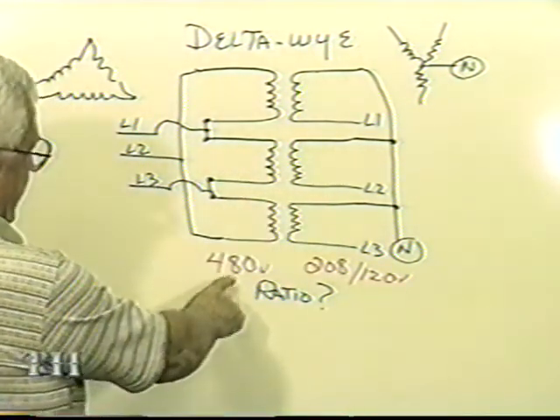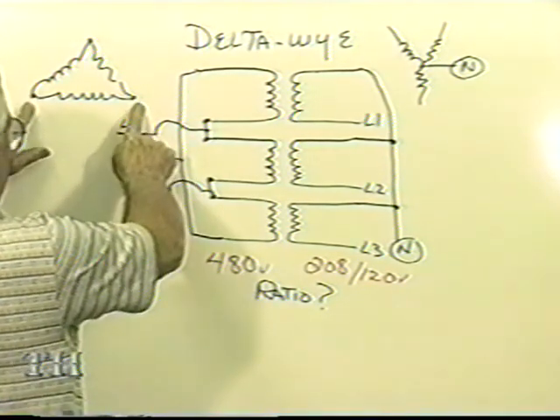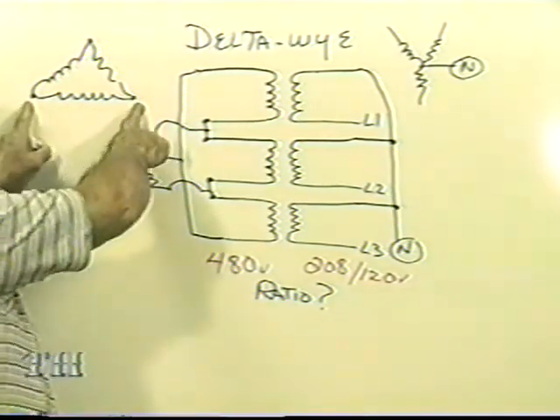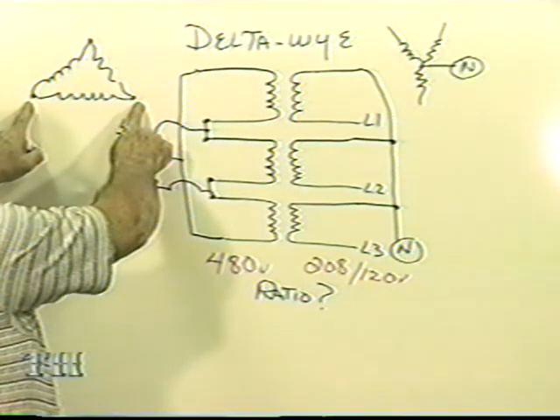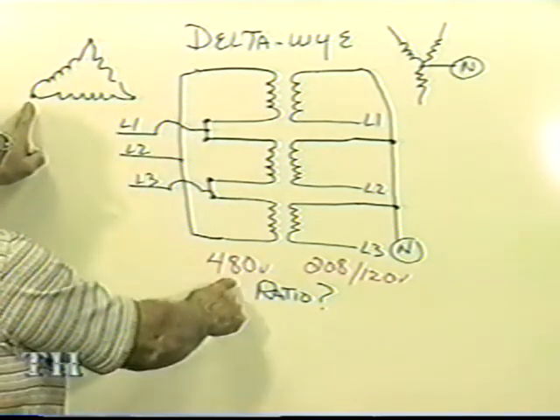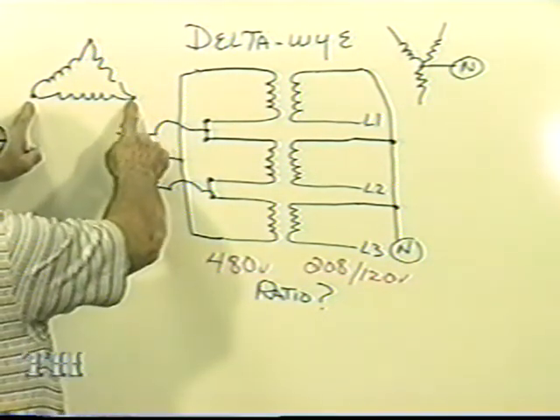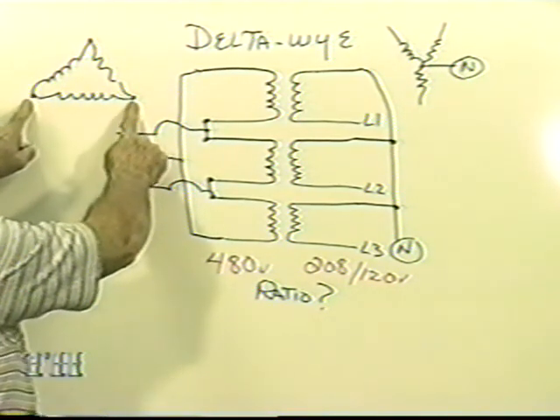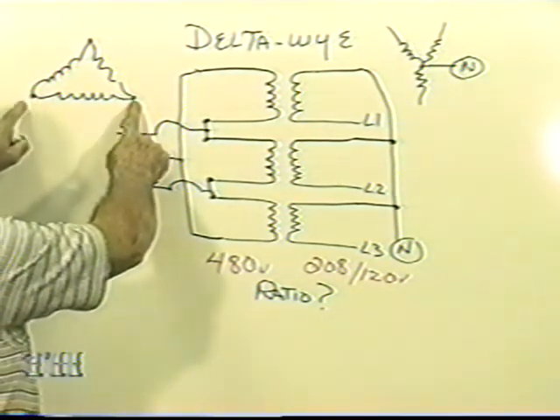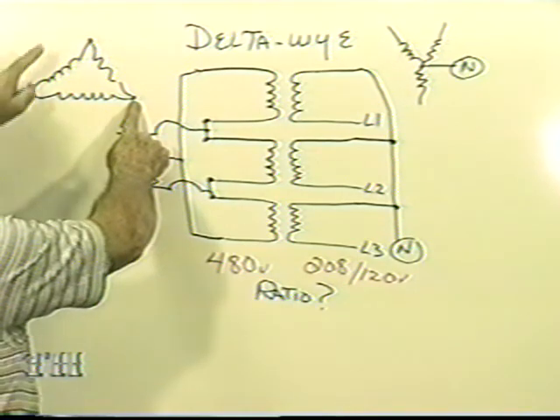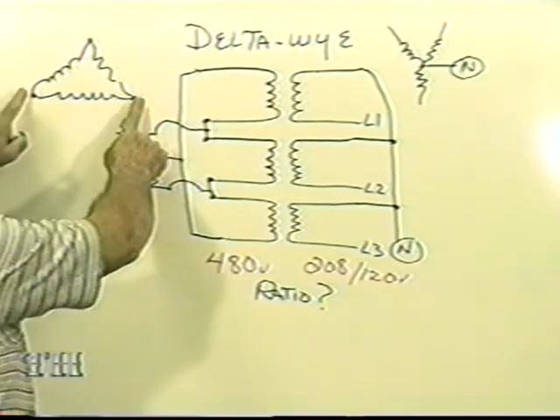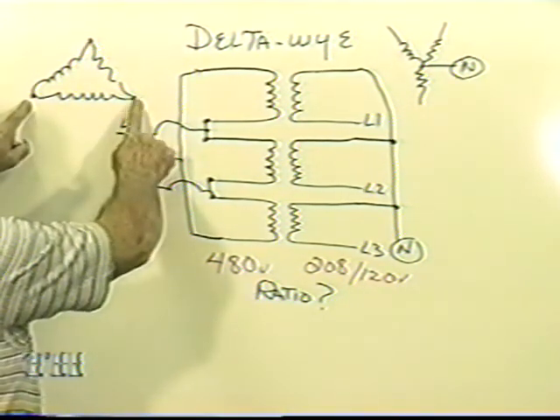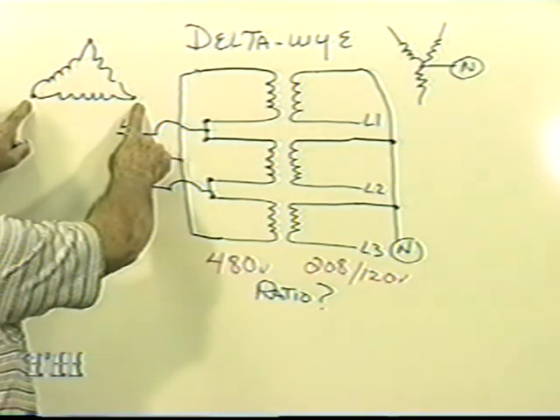See where I said the primary is 480 volts? You put your voltmeter right there, and you're going to read 480 volts. But you have to note where my fingers are. My fingers are from line to line, like line 1, line 2, line 3. I'm reading line to line on a delta primary, 480 volts.